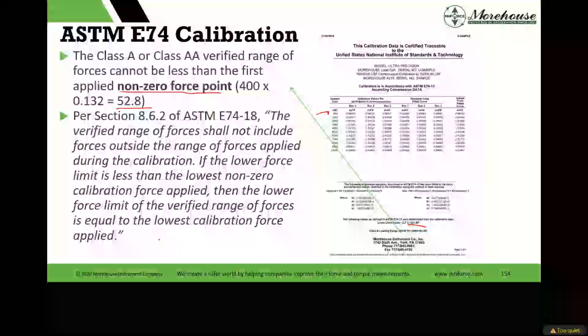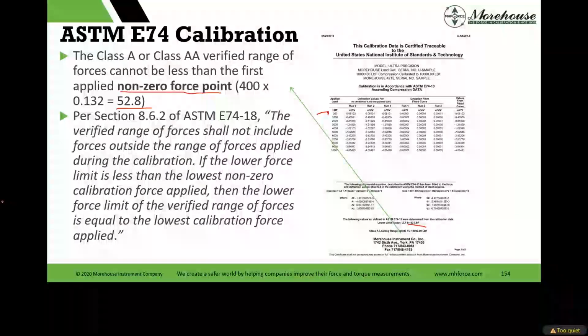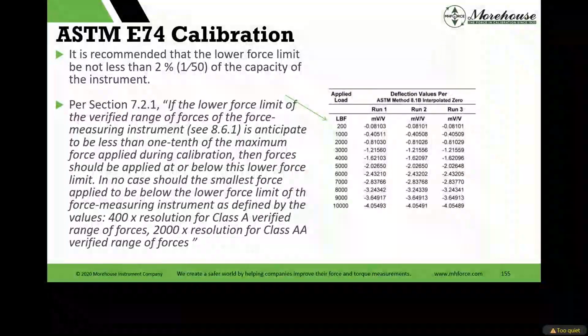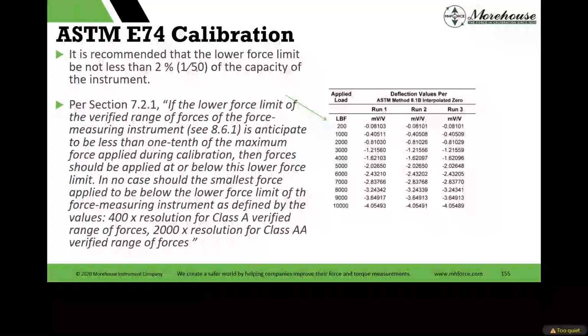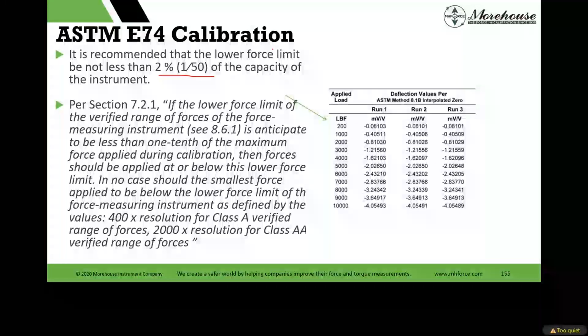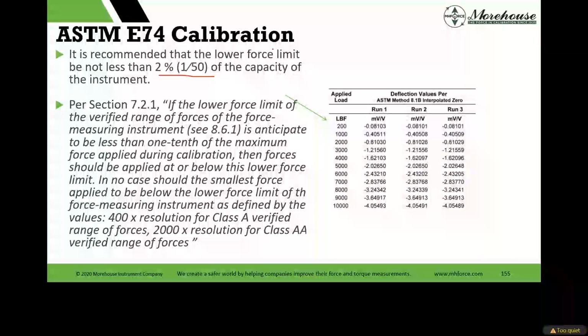And I know people in the field want to go as low as possible, so you basically get to the point where you ask your calibration provider to go as low as they possibly can for you. But then ASTM recommends 2%. ISO 376, it's a shall instead of a recommend. So ISO 376, if anybody's using, that's international standard, you cannot go lower than 2%.